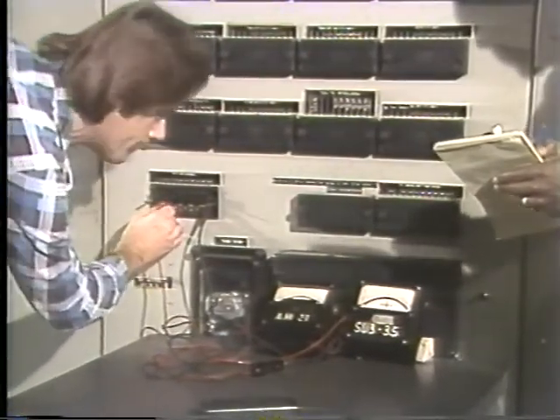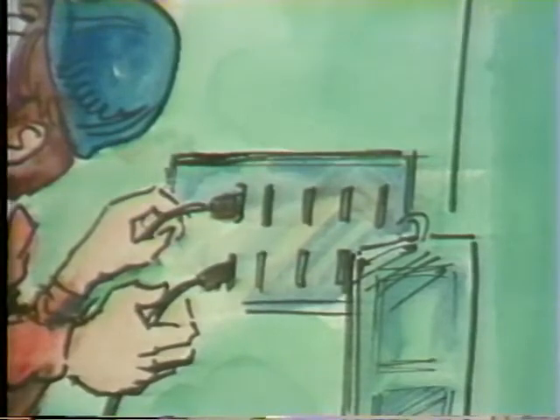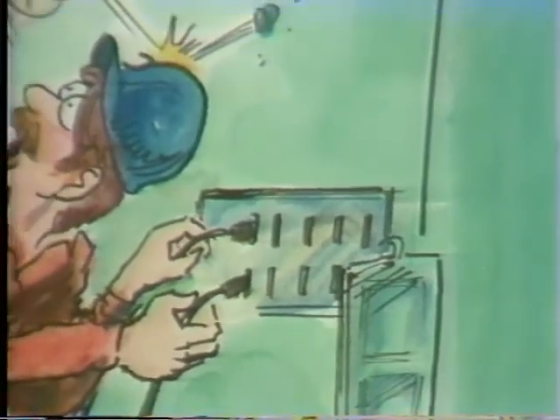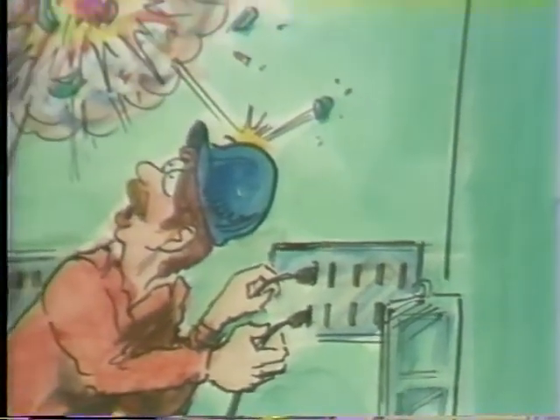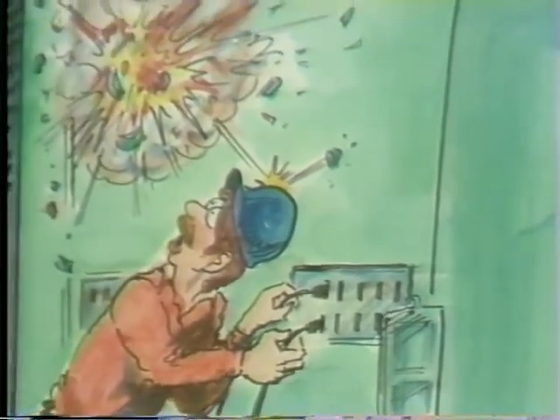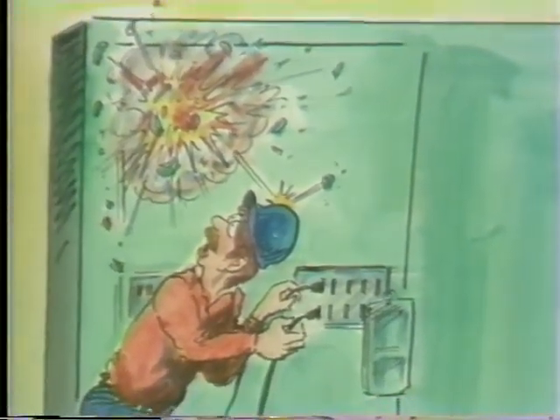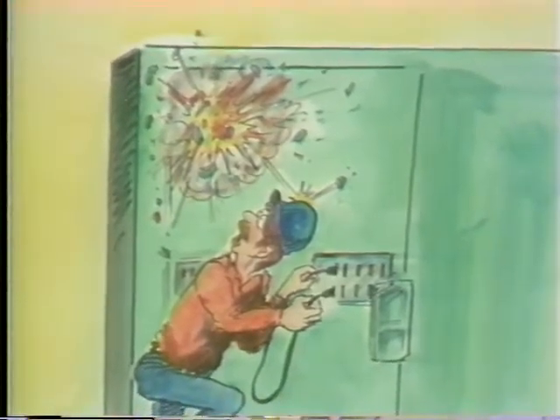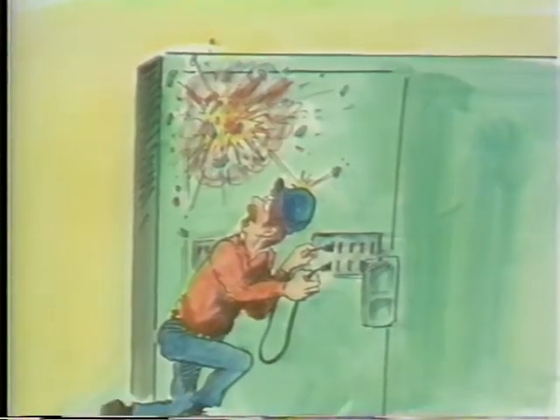There's another difference too. When you're removing a voltmeter from a potential transformer, you don't short the secondary. That'll create enough current to blow up the transformer and everything connected to it, which you might not notice when you're knocked unconscious by the shock. If you have to replace a voltmeter or work on a panel that's fed by a potential transformer, you open the transformer primary instead. That way you can avoid accidental shorts and the high current shocks they cause.